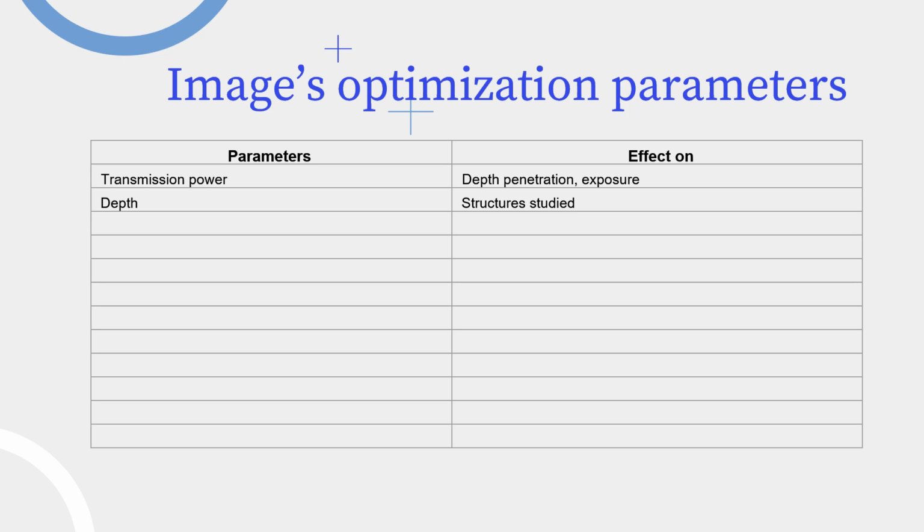A big depth of field will be chosen to study deep structures and a smaller one for superficial structures. Focus is another important parameter to optimize image.